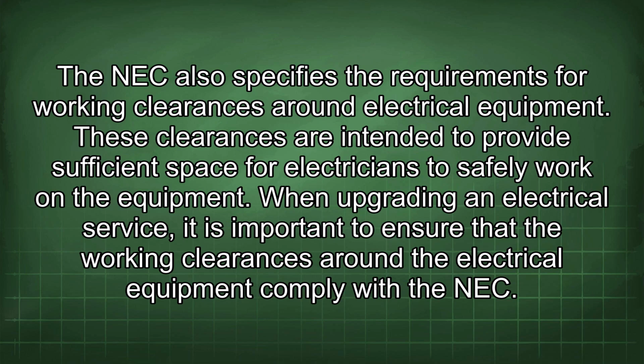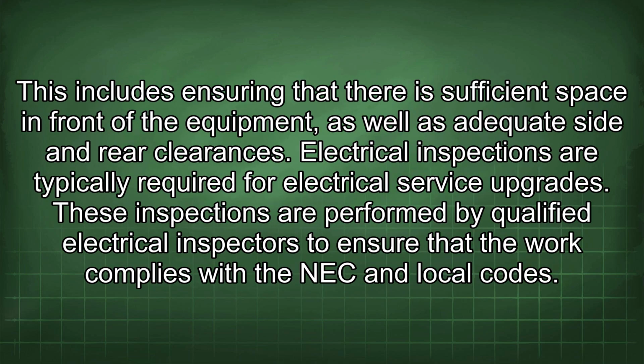The NEC also specifies the requirements for working clearances around electrical equipment. These clearances are intended to provide sufficient space for electricians to safely work on the equipment. When upgrading an electrical service, it is important to ensure that the working clearances around the electrical equipment comply with the NEC. This includes ensuring that there is sufficient space in front of the equipment, as well as adequate side and rear clearances.